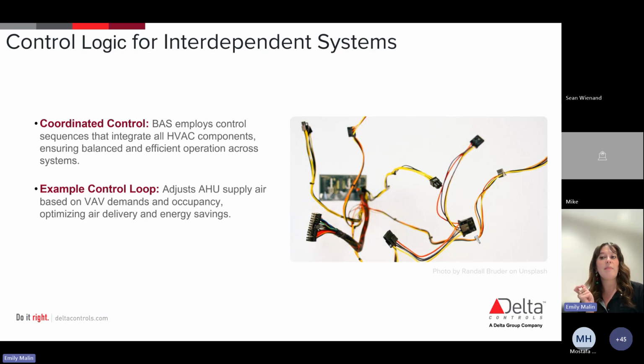Again, we talked a little bit about control loops in BAS 102, but just to remind you, and to put that in the context of how this works in play. A control loop in a building automation system is going to be this automated process that's actually regulating specific building systems or components by maintaining your desired conditions. And what we talked about on desired conditions in 102 was going to be kind of your inputs, right? So that's going to be your temperature, your humidity, your pressure, those sensor-based control pieces.